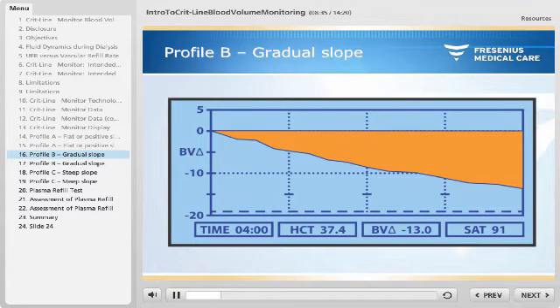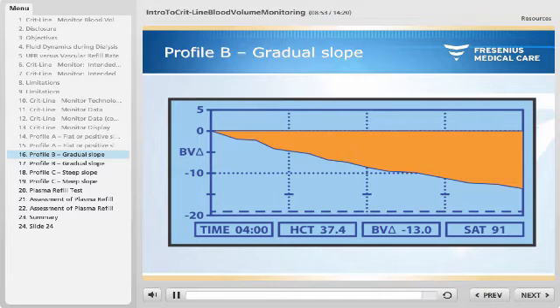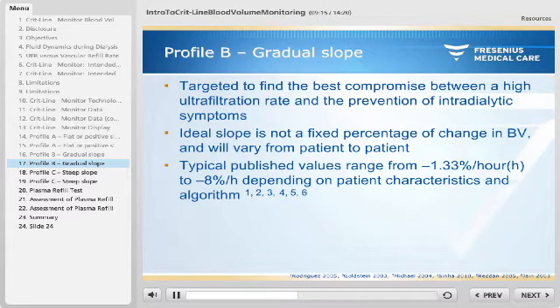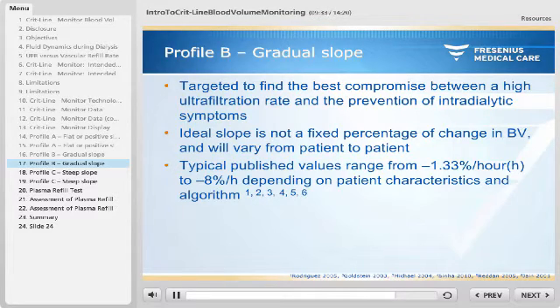The second example shows a gradually declining curve with a relatively constant blood volume change of minus 3.25 percent per hour over four hours, ending at a relative blood volume change of minus 13 percent — referred to as blood volume profile B. A gradually declining profile B has been targeted to find the best compromise between a high ultrafiltration rate and the prevention of intradialytic symptoms. The ideal slope varies from patient to patient; typical published values range from minus 1.33 percent per hour to minus 8 percent per hour depending on patient characteristics and algorithm.